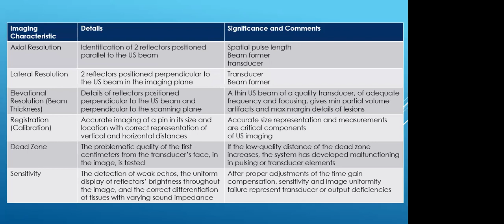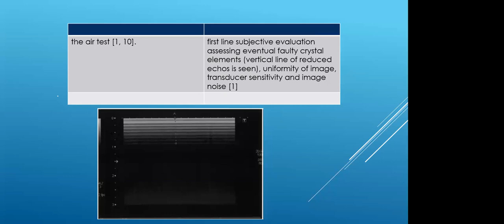These are the basic things that you would do in your QA system, right? And remember, if you're going to do that, then it must also be in your baseline when you started off with your QA or acquisition of the new equipment, right? I won't go through the other part there, but for those that might want it, I will probably share the slide at the end of the day. Right, this is the air test, which is very basic, but it's very good in terms of measuring uniformity and sensitivity, and also picking up image noise, right?